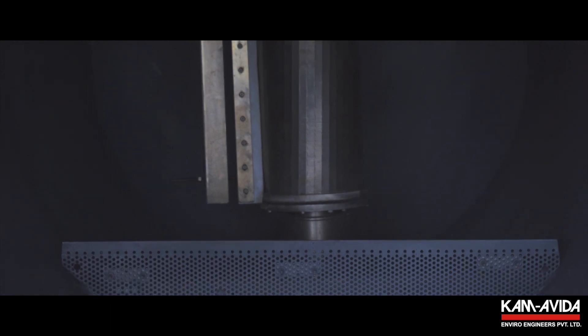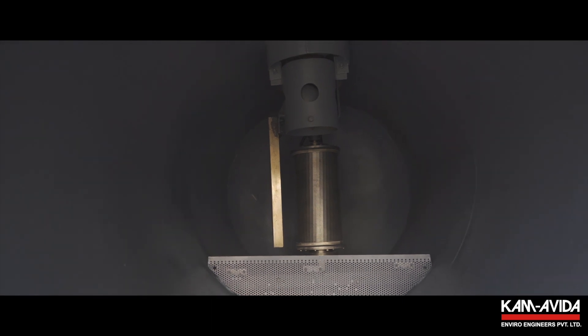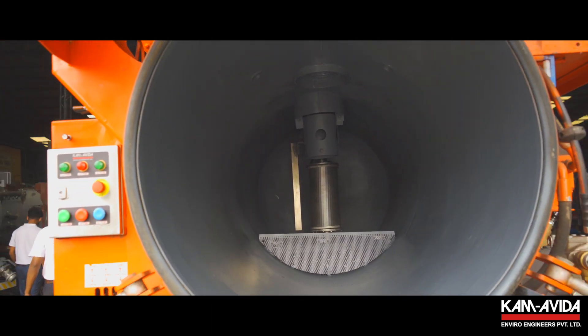The filtration system is the heart of the KAMBI Mini Recycler. With 200 lpm of output, the three-stage filtration system is capable of filtering sewage water up to 50 microns. The robustly constructed 100-micron coarse filter element is made from stainless steel and is rotary and self-cleaning.